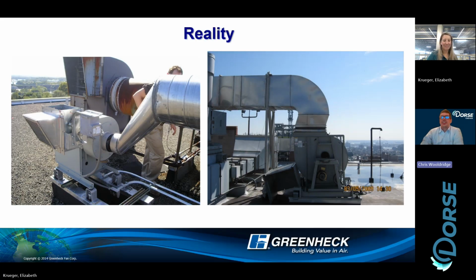So focus on your discharge orientation, because in this instance, had you done a reverse rotation of the fan wheel and did a top angled up, or even in this case, a bottom angled up, you could have turned that hard 90 into a not quite as bad, but still bad, 45-degree, kind of breaking the back. So it's still not good. It could be better, but this could have been a much better performance. And to your owner, what do you do to fix this scenario? You speed up the fan, you use more motor power, assuming you have enough horsepower available. You might have to buy a new motor. But no matter what, the owner is paying for that volume loss, that pressure loss that's being generated there.